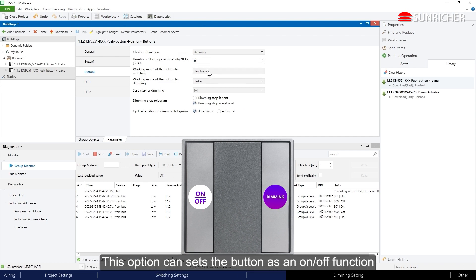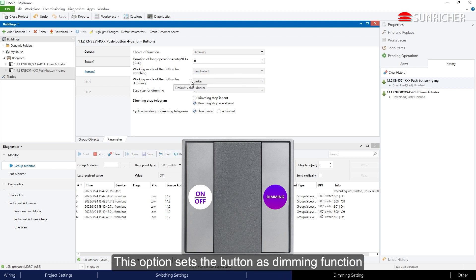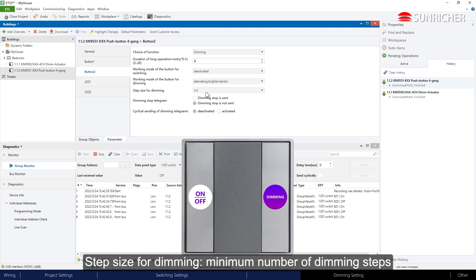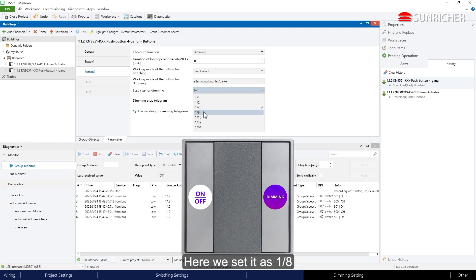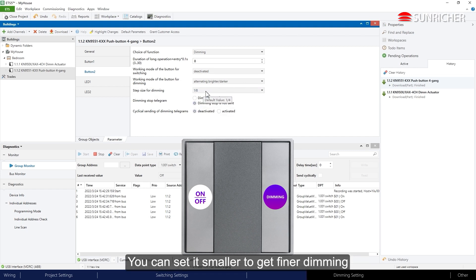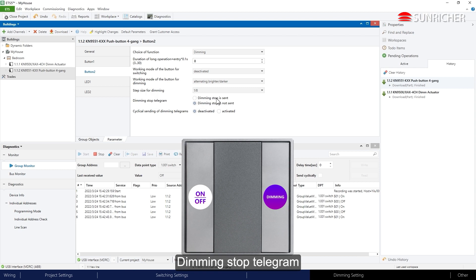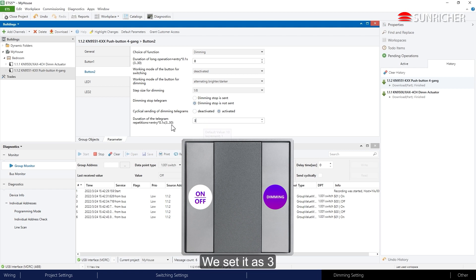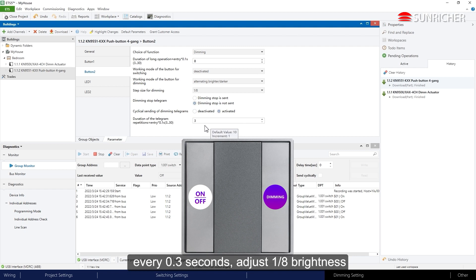This option sets the button as an on/off function, and this option sets the button as a dimming function. Step size for dimming: set the minimum number of dimming steps to one eighth — you can set it smaller to get finer dimming. Activate the cyclical sending of dimming telegrams and set it to 3, meaning when long-pressing the button, every 0.3 seconds it adjusts brightness by one eighth.